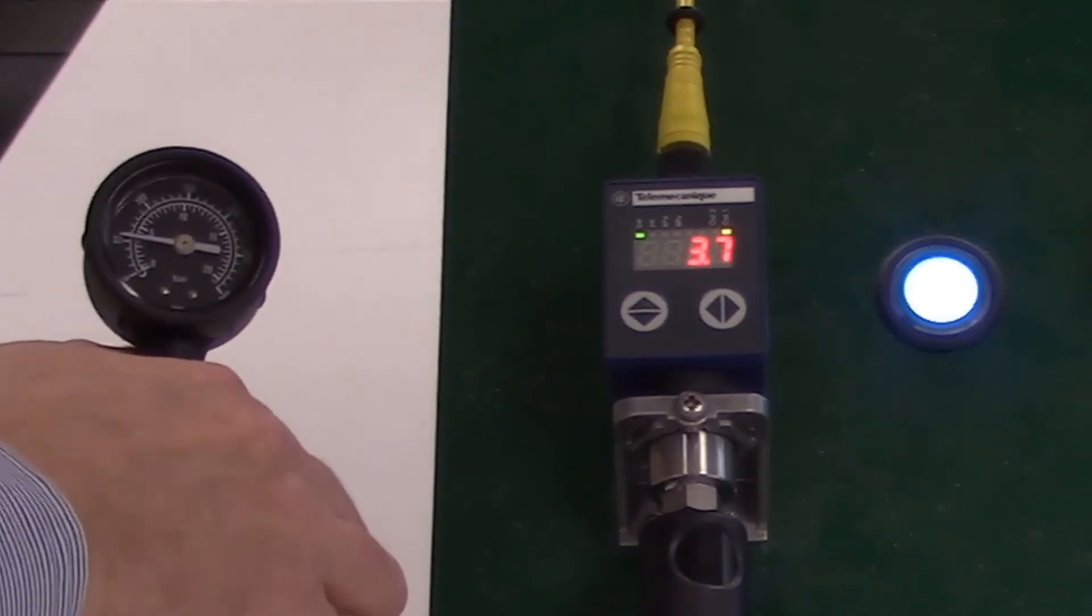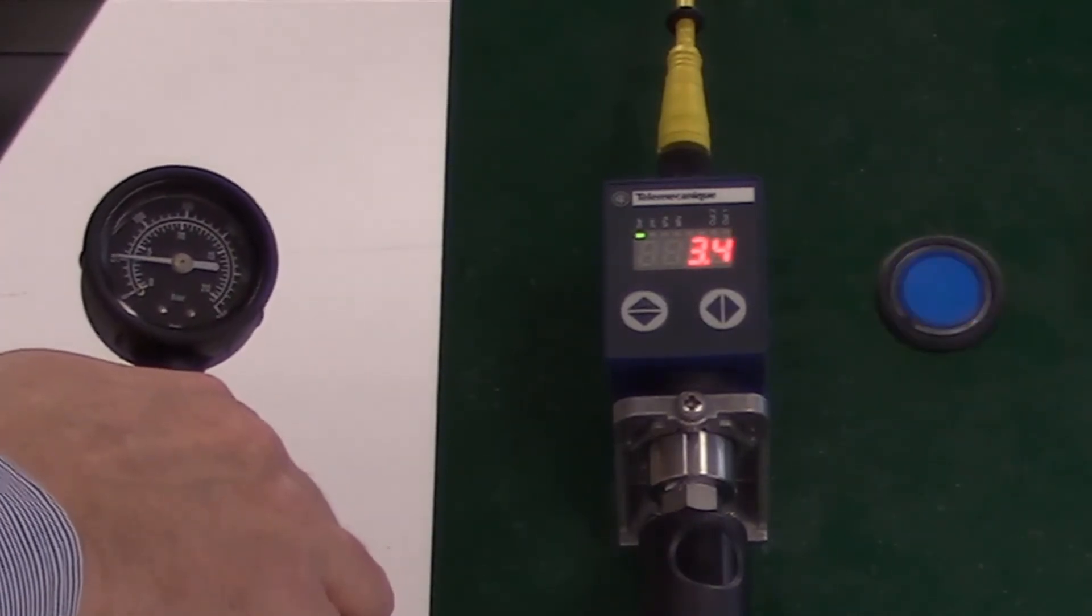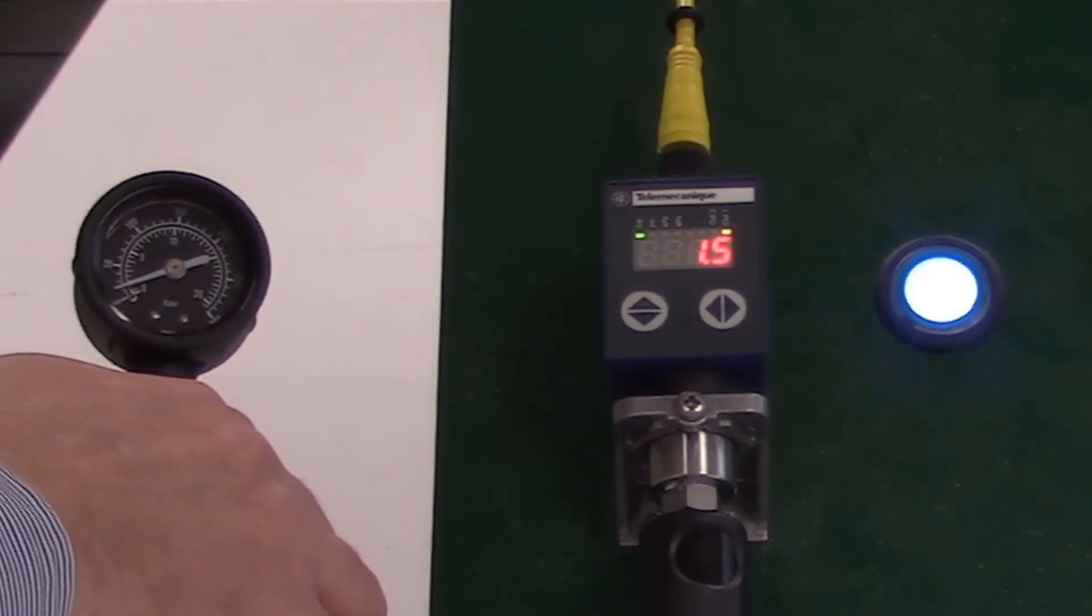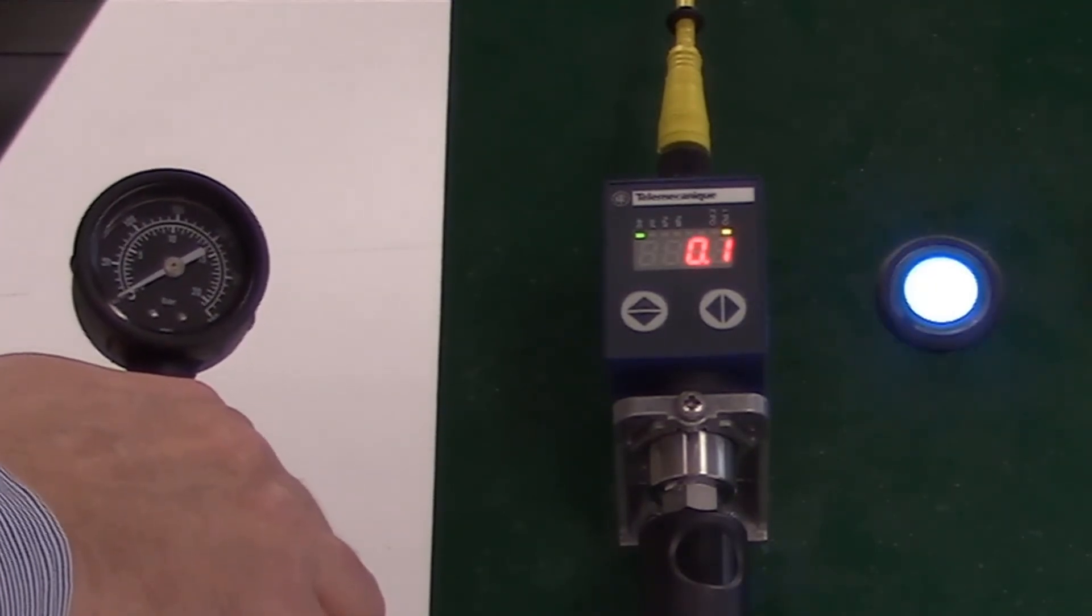As the pressure then is released from the system, below 3.6 bar the contact will turn off, and below 1.5 bar the contact turns on again. Thanks for watching.